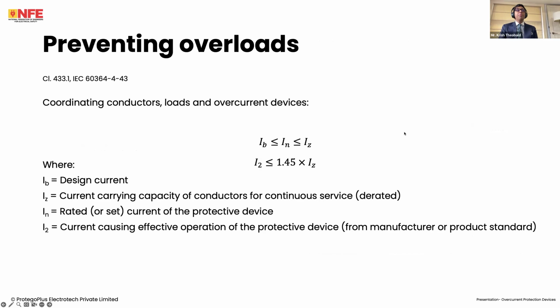Now, how do we prevent an overload from occurring? Well, the first thing is conductors, loads, and overcurrent devices need to be coordinated. So we have IB shall be less than or equal to IN shall be less than or equal to IZ. Now, what does this mean? Unfortunately, in practice, very often we say, okay, this is the load current, this is the cable we choose. The protective device is chosen much later on. Unfortunately, that's not the right way to go about this.